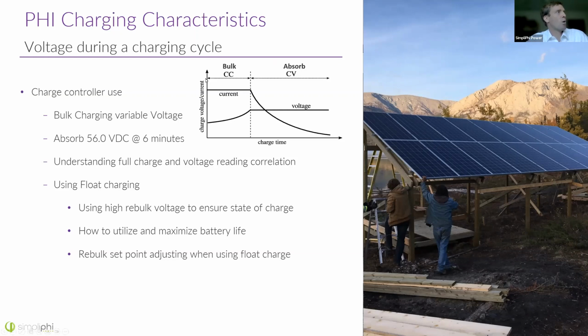And notice in this bulk phase, that's a constant current process. The current is constant, whereas the voltage is increasing because you need to put more pressure to get more charge into that battery as it fills up. Once the battery reaches a certain voltage, the bulk cycle ends and we start the absorb cycle of the battery. The absorb cycle is really a top-off cycle of the battery. The setting for this on our batteries is 56 volts DC.